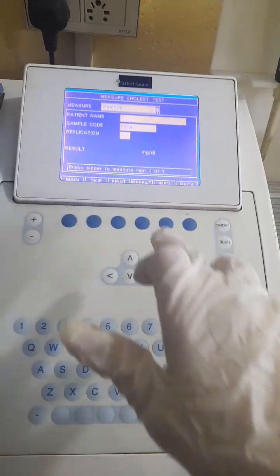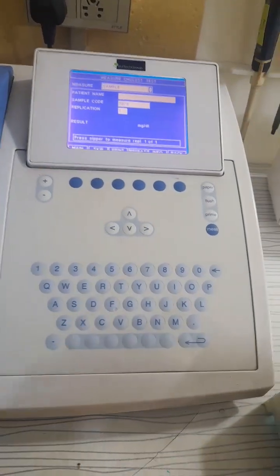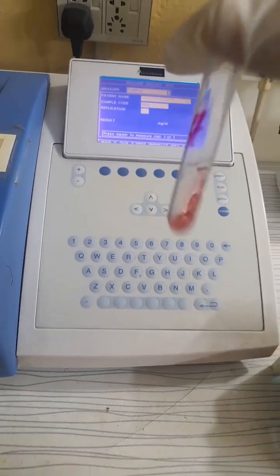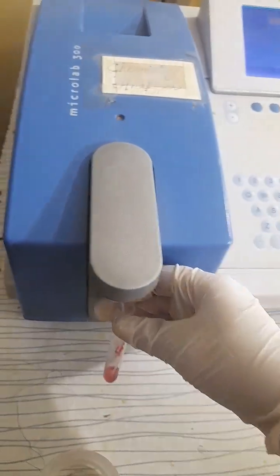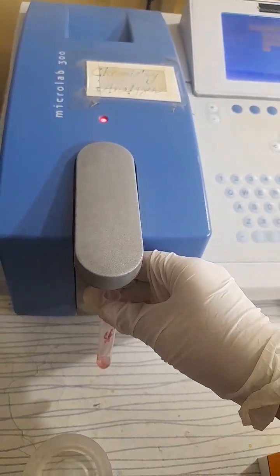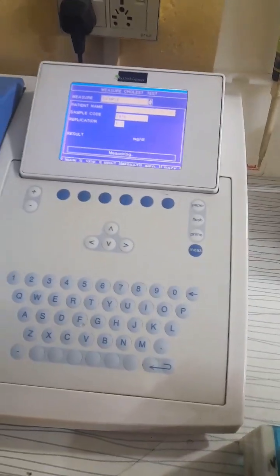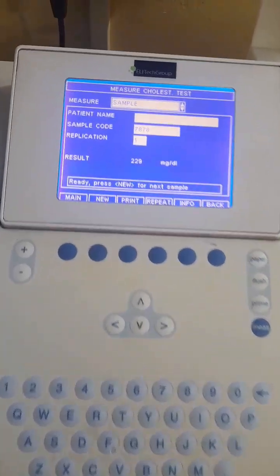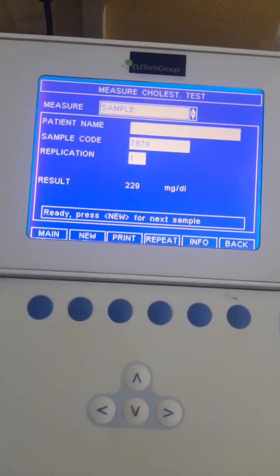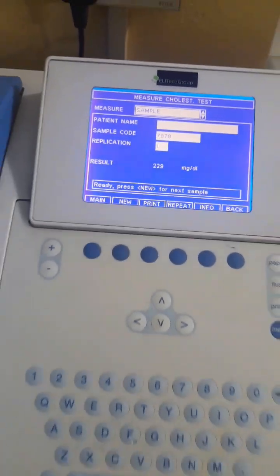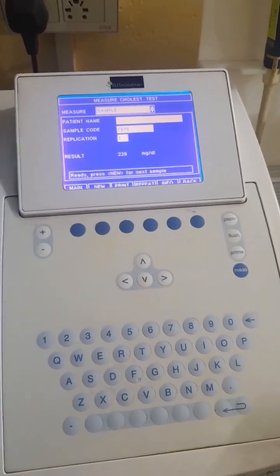As you see, the standard is already mentioned: if run as a sample, it will be 200 milligrams per deciliter. If the standard run as a sample shows 201, we can consider it. If it is 205 or 204, it will not be considered. As you see, my standard ran as 229, which is not acceptable.